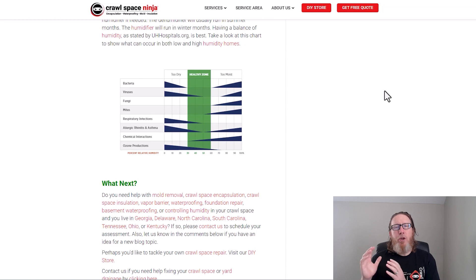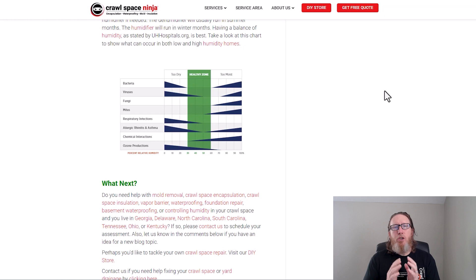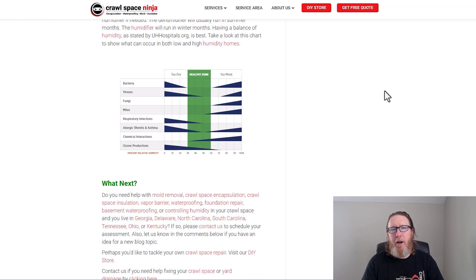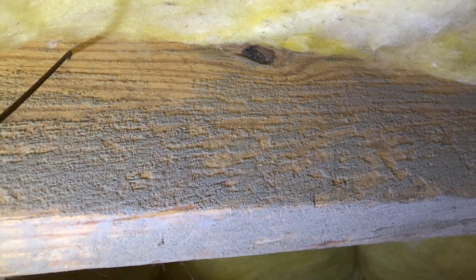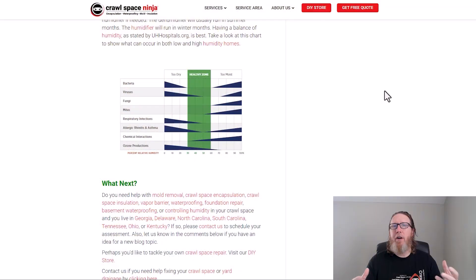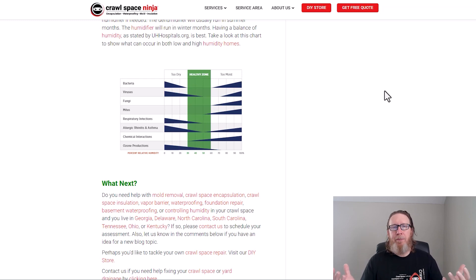What you want to do is use lower humidity to address the mold and to prevent it from returning. But the simple fact of installing a dehumidifier in your crawl space and cranking it down to 50% is not going to kill that mold. It is just going to sit there and wait — wait until you get a plumbing leak, until something happens to the dehumidifier. It's very patient; it'll stay there forever until a moisture problem happens.